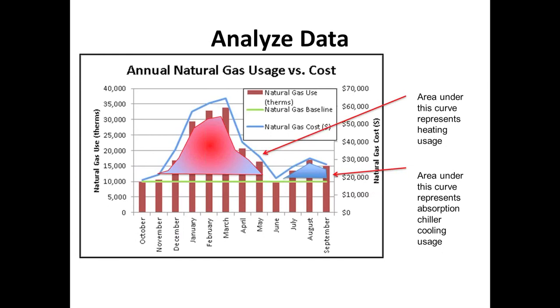that green line for every month, that's going to be a lot of just basic natural gas usage, a lot of domestic hot water usage. It's a hospital, so there's a lot of showers and baths being taken, a lot of hot water usage. There are 4 cafeterias in the specific building. So there's a relatively high natural gas baseline. Then also during the summer, you're going to see where those absorption chillers were driven to provide cooling for the building. So we also have a peak in the cooling.